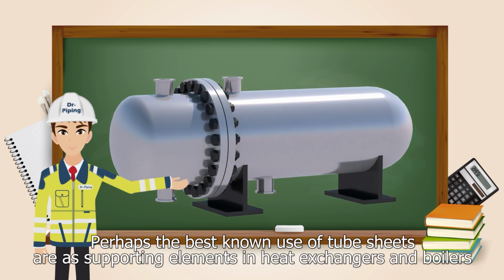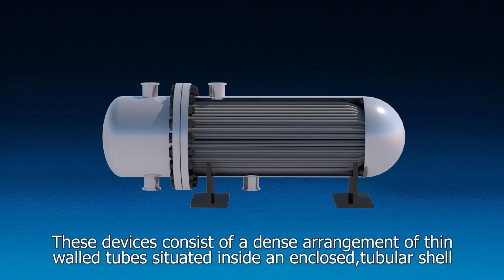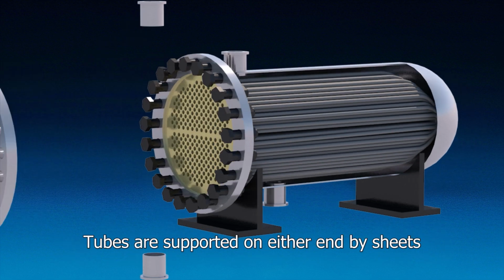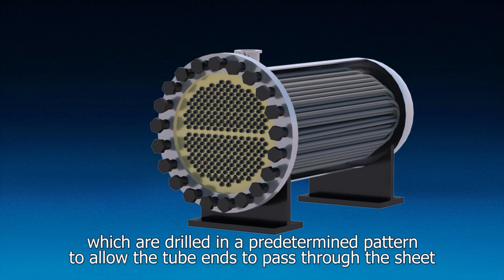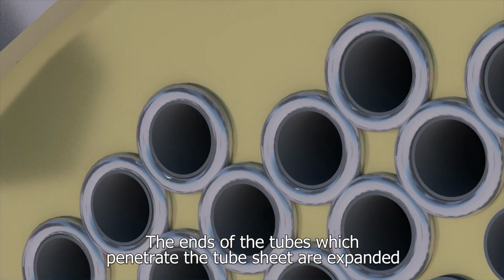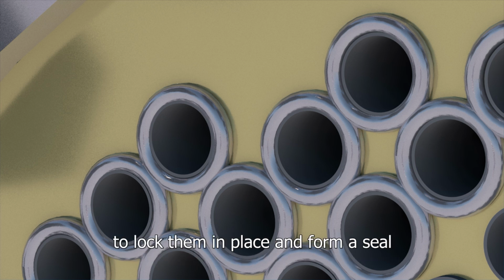Perhaps the best known use of tube sheets is as supporting elements in heat exchangers and boilers. These devices consist of a dense arrangement of thin-walled tubes situated inside an enclosed, tubular shell. Tubes are supported on either end by sheets which are drilled in a predetermined pattern to allow the tube ends to pass through the sheet.